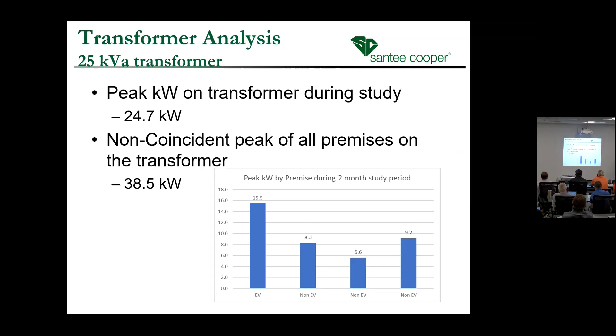But the coincident peak was 24.7 kW, so you're getting pretty close to capacity there. Non-coincident peak, which is what this would all add up to be, would be 38.5 kW. So I pulled up when they hit the peak—what half-hour period they actually hit it—and it was this half-hour period. You can see the EV contributed to over half of that coincident peak on the transformer.